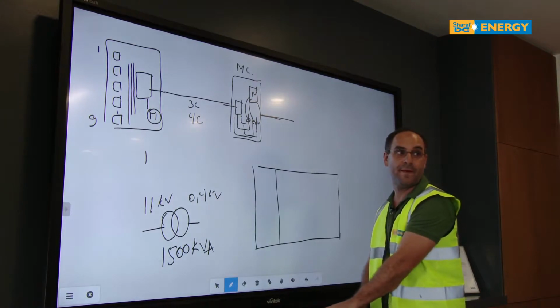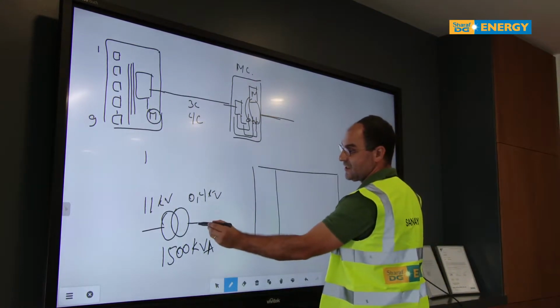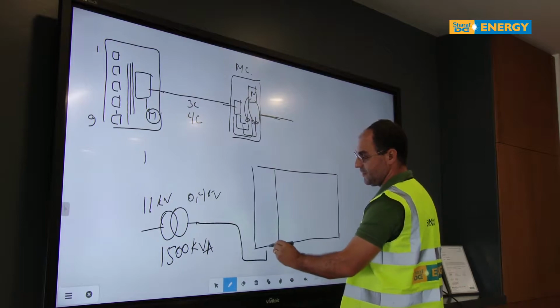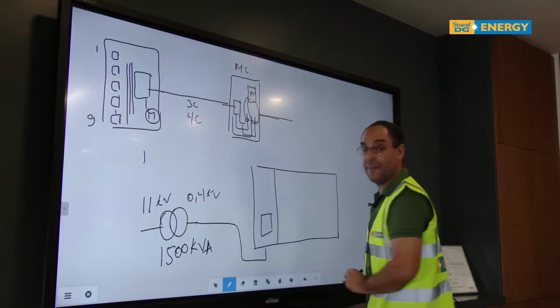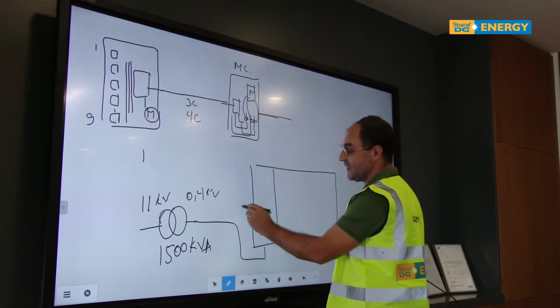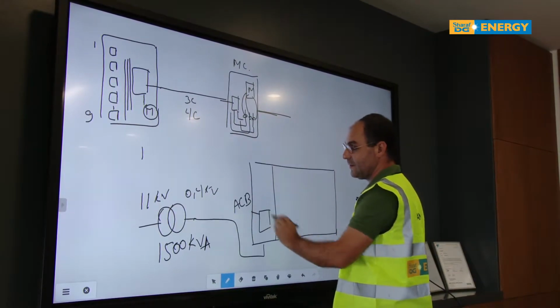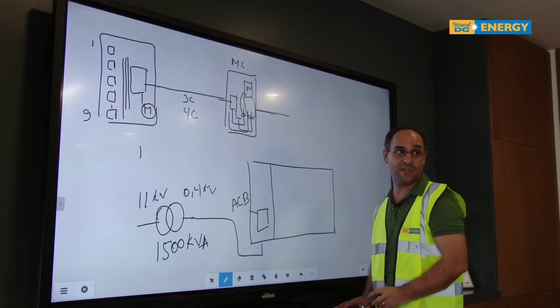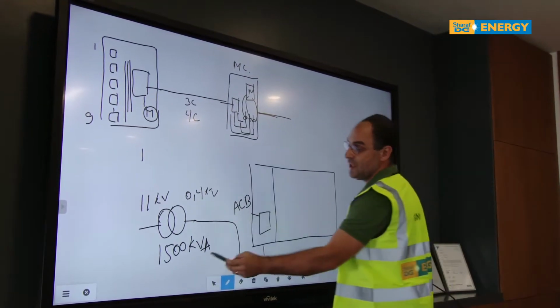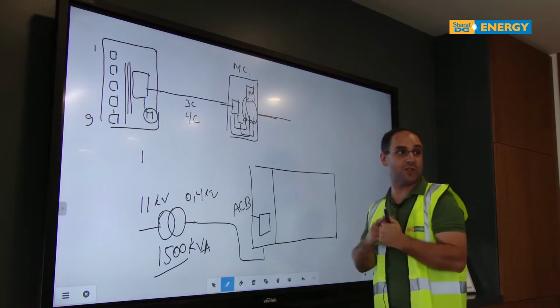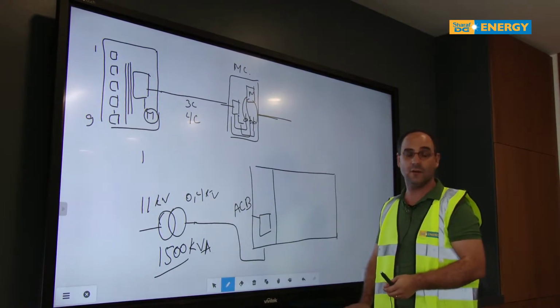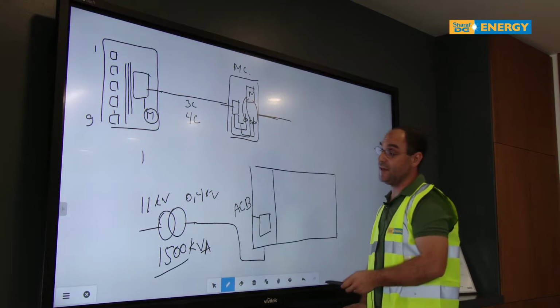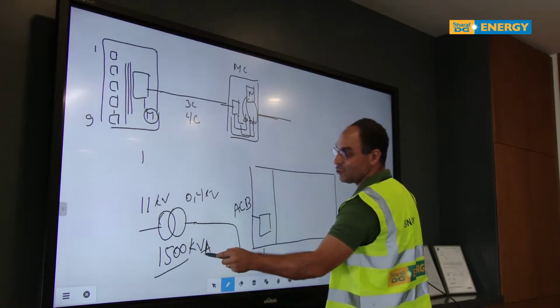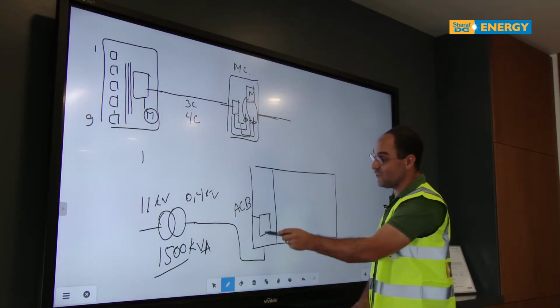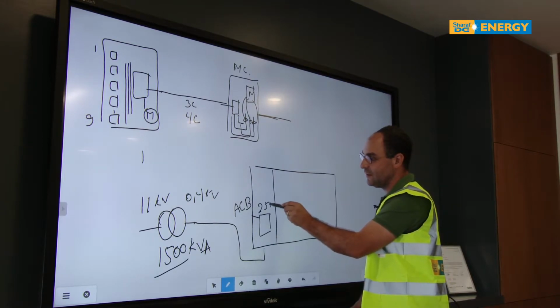This transformer delivers into a main breaker, which you guys know as ACB, rated for that power. Because usually, if there is a short between phase and neutral, or phase to phase, you will realize the amount of current generated is very close to the 2,500 amps that you put here.